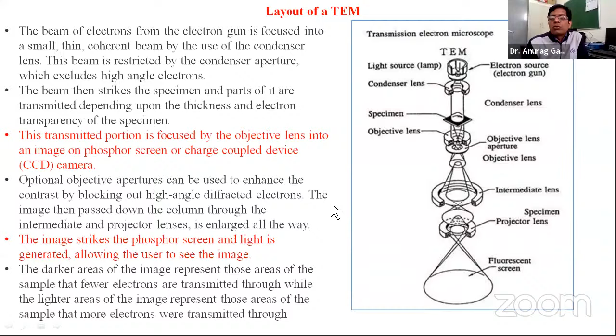If it is not electron transparent, a very small amount of the beam will transmit, so you will not get a good image. This transmitted portion is focused by the objective lens into an image on a fluorescent screen, and then with the help of the CCD camera, the charge coupled device, you can capture the image, and that image can be used for further analysis of the sample. So this is the working of transmission electron microscopy.